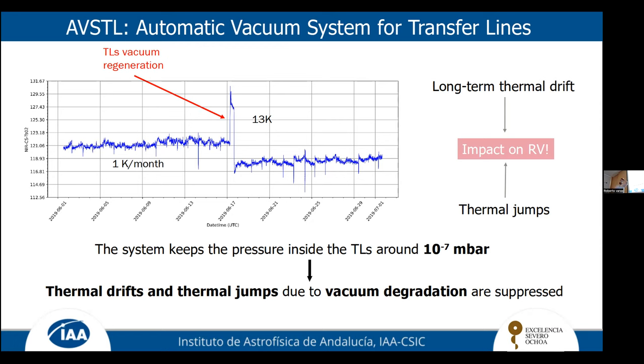We basically have vacuum conditions on the system, okay? And if you perform vacuum on an instrument or a system and you let it go without doing anything at all, we lose these vacuum conditions over time. We have a degradation of the vacuum. So when the vacuum is lost, we have a bigger heat load coming from the convection.